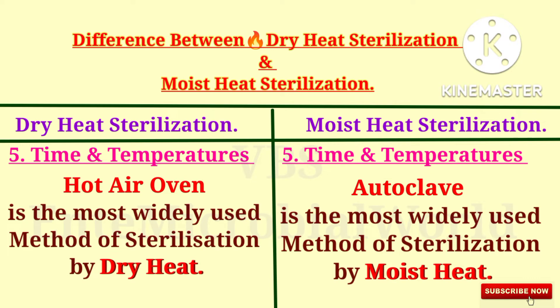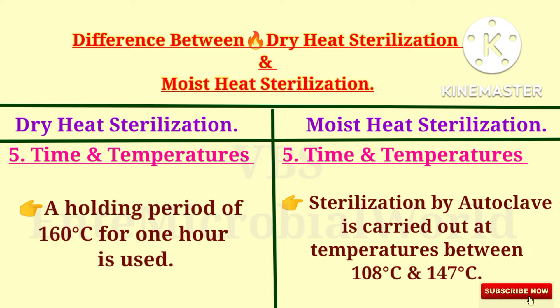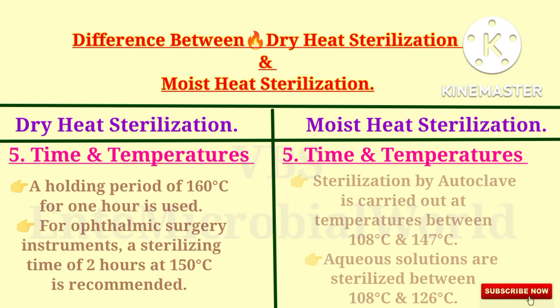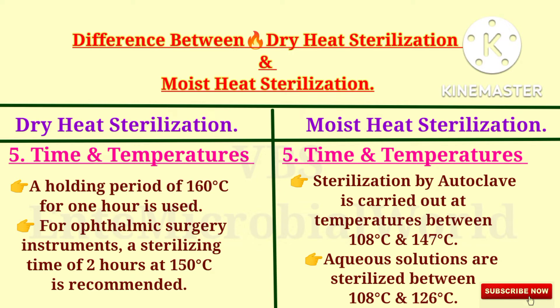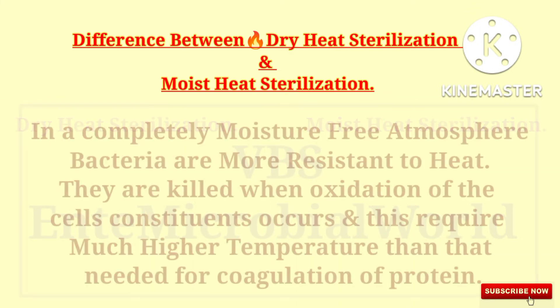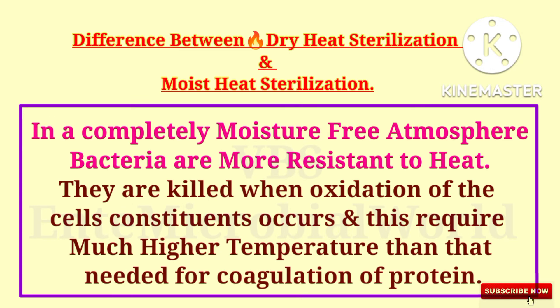Autoclave is the most widely used method of sterilization by moist heat. Sterilization by autoclave is carried out at temperatures between 108 degrees Celsius and 147 degrees Celsius. Aqueous solutions are sterilized between 108 degrees Celsius and 126 degrees Celsius.